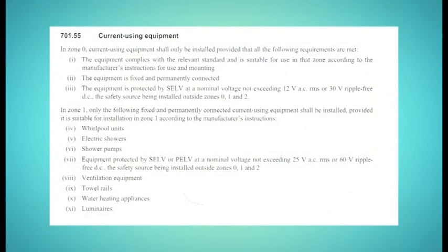Next we have suitability of equipment for installation in a particular zone. For example, switchgear and control gear. Well, here the light switch and the fan isolator are actually out of the room, so this is not applicable. Our final box for this location is suitability of current using equipment for a particular position within the location. So here we're checking the requirements of regulation 701.55 are complied with and includes equipment such as electric showers and any luminaires. So for this installation, it will be a not applicable.